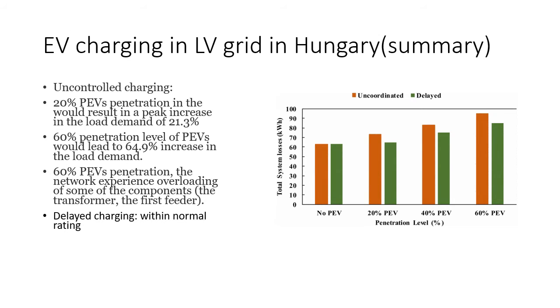In this slide we have a summary of the findings on the electric vehicle charging effect in the low voltage grid in Hungary. For uncontrolled charging, we can see on the right that the total system loss is higher in all three cases, and at 60% it's quite concerning. With delayed charging it gets reduced by some. Regarding that, 20% electric vehicle penetration in the grid would result in a peak increase in the load demand of 21.3%. That's for uncontrolled charging.